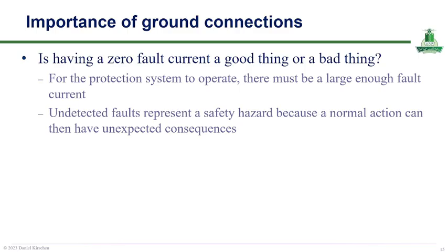Okay, this slide raises an important practical question about grounding. Is having zero fault current actually desirable? While it might seem beneficial at first, since no current implies no immediate damage, it is in fact a serious problem from a protection standpoint.